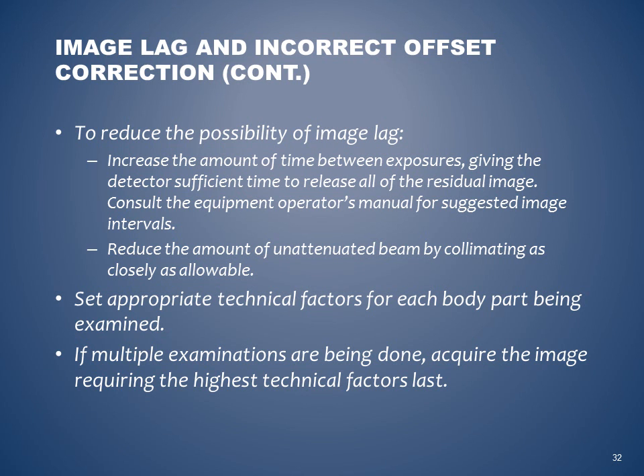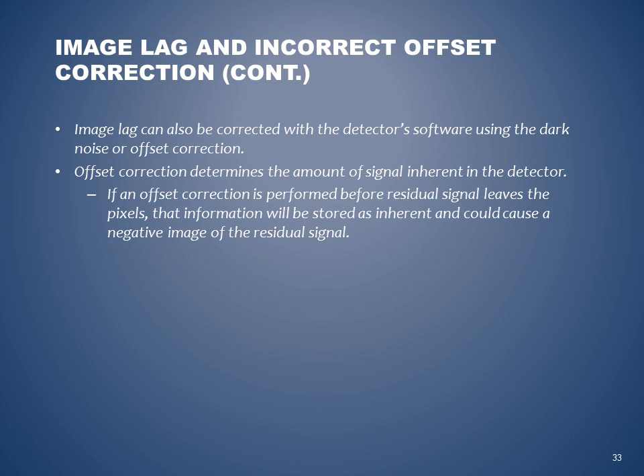To reduce the possibility of image lag, increase the amount of time between exposures, giving the detector sufficient time to release all of the residual image. Consult the equipment operator's manual for suggested image intervals. Reduce the amount of unattenuated beam by collimating as closely as allowable. Set appropriate technical factors for each body part being examined. If multiple exposures are being done, acquire the image requiring the highest technical factors last.